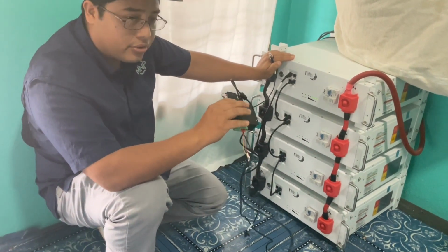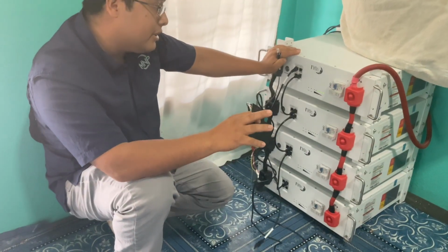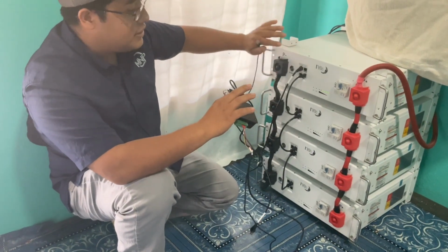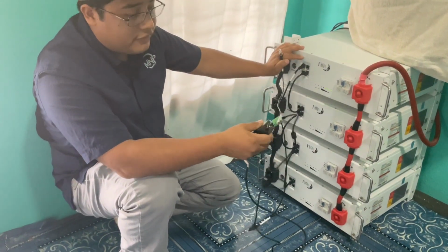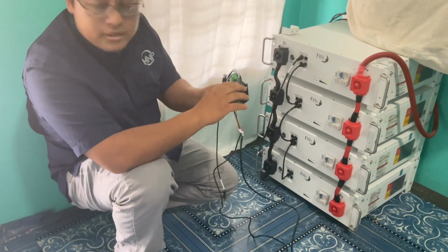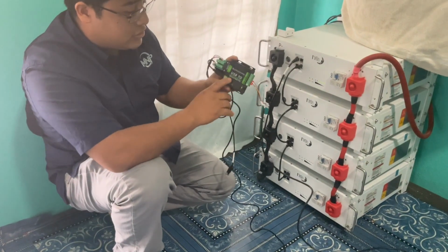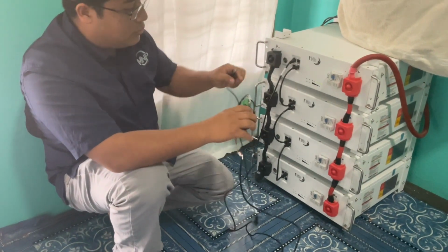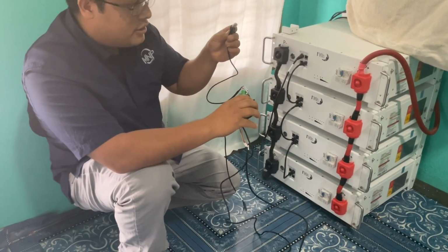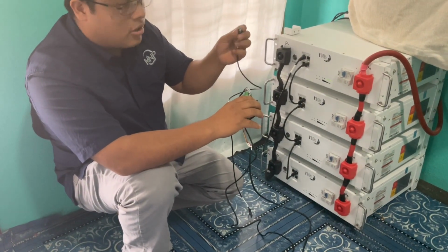It's not for diagnostics, it's not for updating, it's only for communication with the inverter. So do not try the 485. If your tool is a 485 converter, it will not work. It's got to be RS-232 with the adapter board and the Ethernet cable with the RJ45 jack.